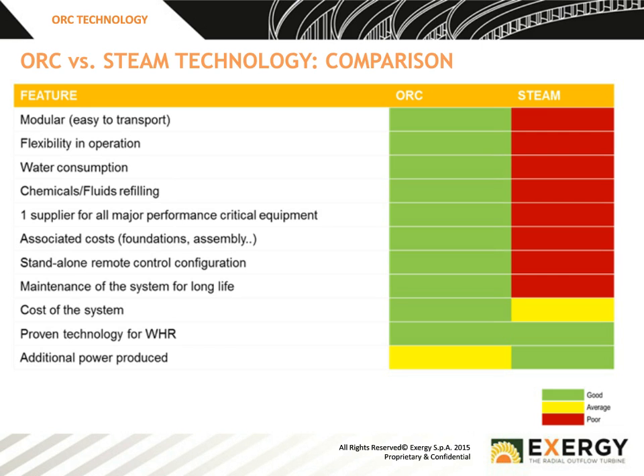Okay, so moving on from that, we then have maintenance, which I think I've already covered, and cost of the system. So at the right size, ORC is okay and can be significantly cheaper than a good quality steam turbine system. And when I talk about those sort of sizes, it's very difficult to put specific sizes because it really depends on the temperatures we're talking about. But I'd say for an industrial process, so a cement plant or a steam plant, up to about 8 megawatts is where ORC tends to give you a better overall cost efficiency solution.